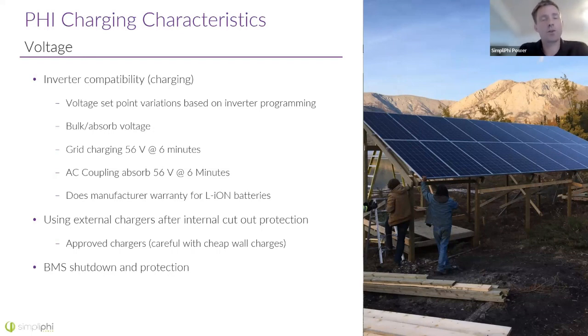So I think the answer to your question would be, yeah, it would be slightly affected. But we're talking about maybe a 10% change in that 3 amps, right? So 3 to 2.7 or something like that. So it's a good question, but for the lithium batteries, especially LFP batteries, there's not a huge variation as the batteries age. Much different from a lead acid battery, where the surface area of the battery is where the chemical reaction is happening, and that surface area can get covered and sulfated, and you lose a lot of the bank with time fairly quickly, even with deep cycle lead acid batteries.